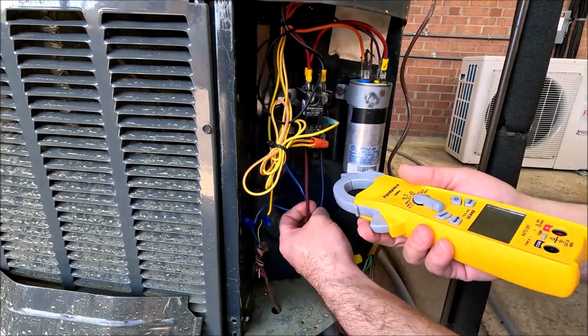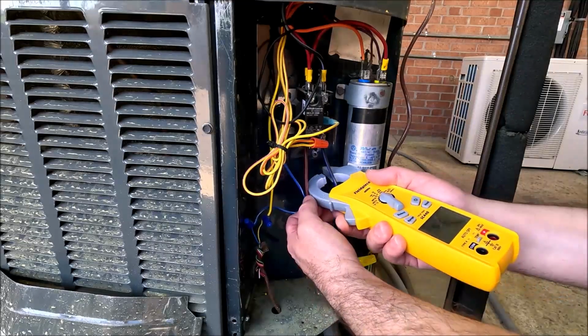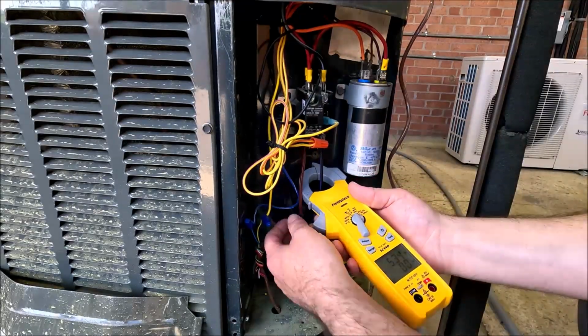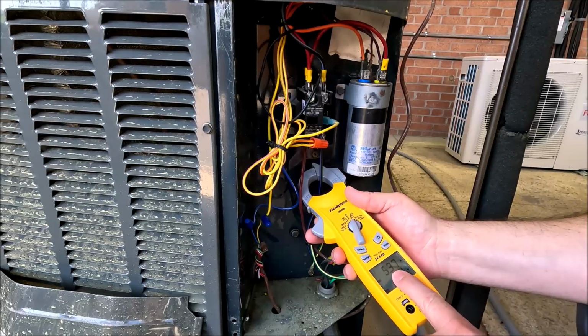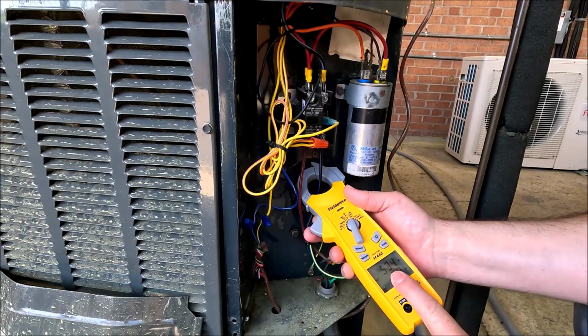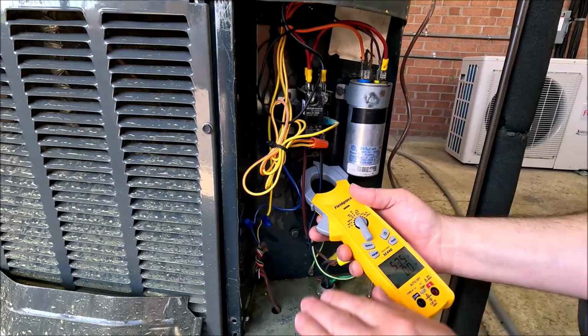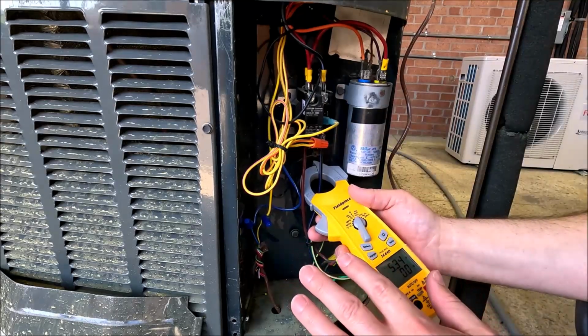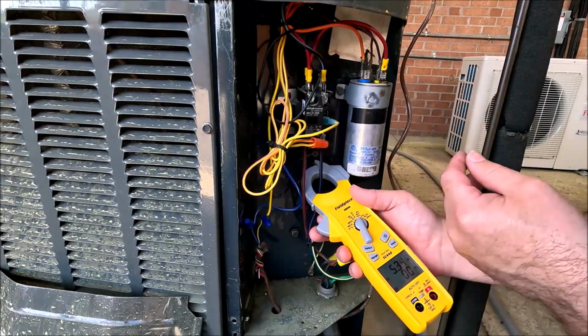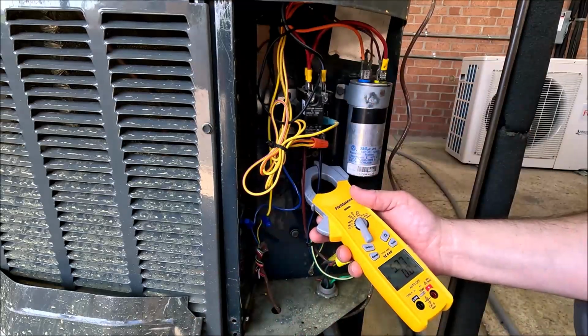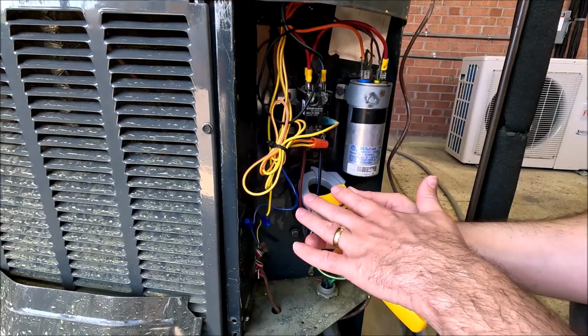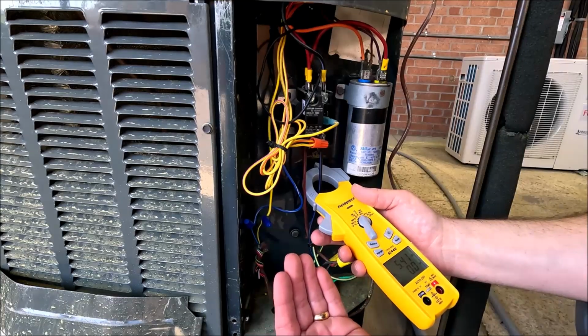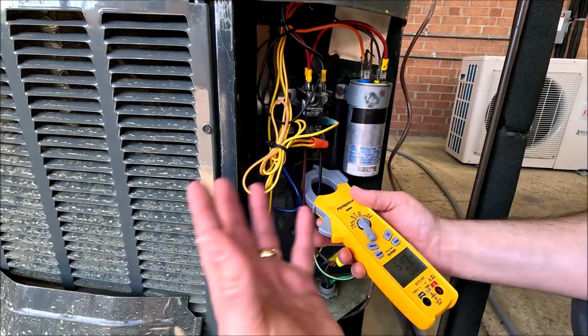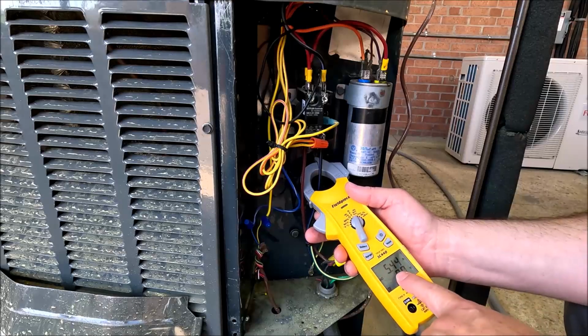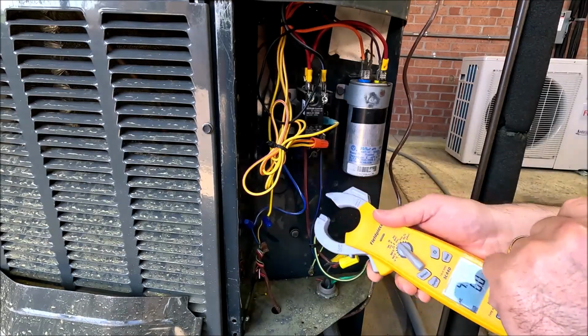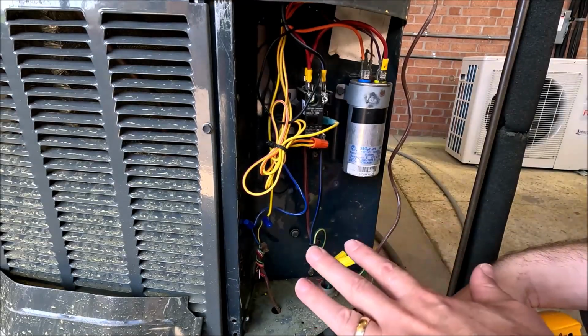So what I can do is I can come on the bottom side of the contactor where I have more room, and I can say, oh look, I got 5.3 amps. Just understand that anything on the load side of the contactor is basically individual components, but on the line side where the power source connects, that's going to be a cumulative kind of deal. So I've got 5.44 amps, but that's both the compressor and the outdoor fan.